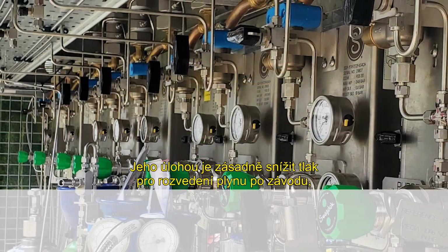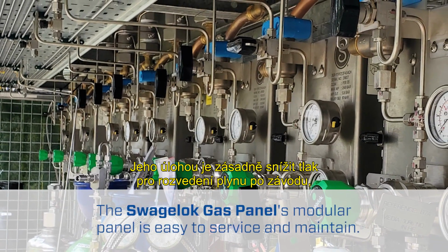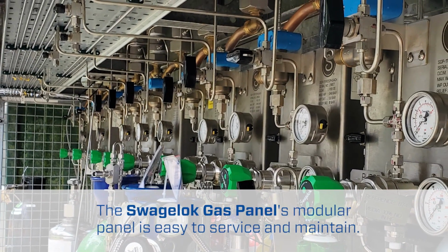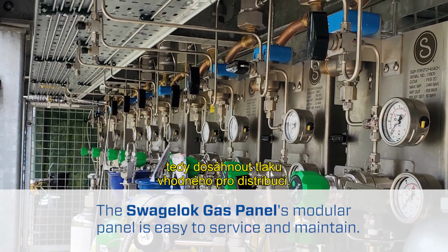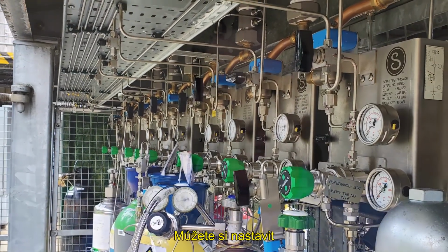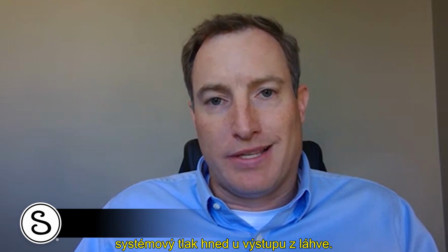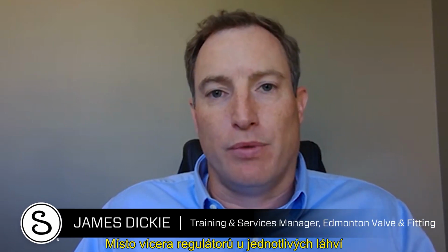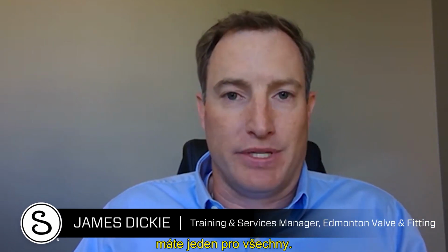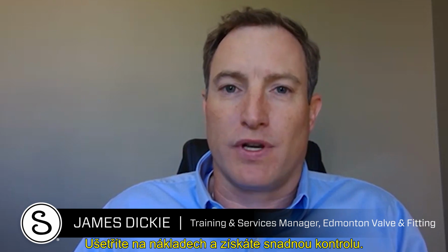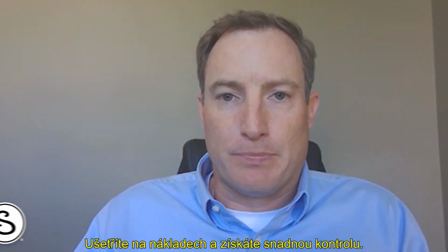It's really there to do that main drop of pressure to get the gas around the customer's site at a comfortable distribution pressure. You can set your system pressure right there as it's coming out of the bottle. Instead of having individual bottle regulators, you have one that'll be used for all of them. So it's a lot more of a cost savings and very easy to control.